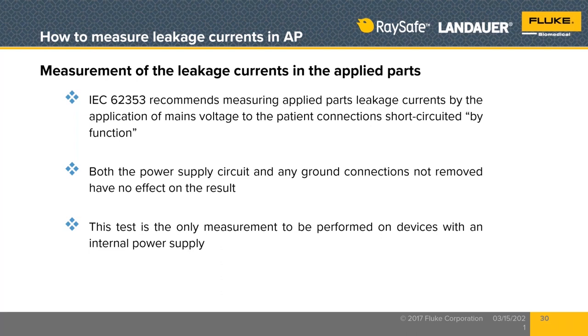So 62353 recommends that we do the measurements the way I've just described. Both the power supply circuit and any ground connections are not removed and have no effect on the result. The test is the only measurement to be performed on the devices with an internal power supply. Okay.